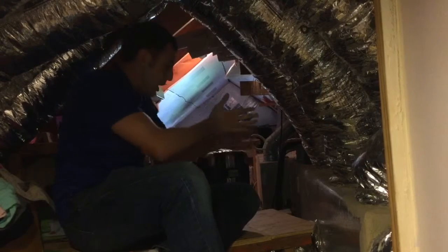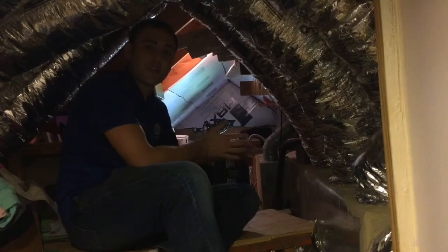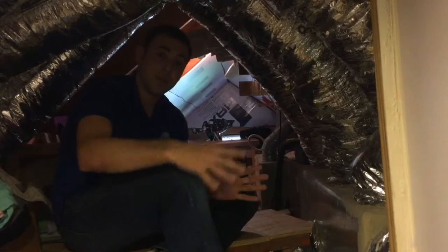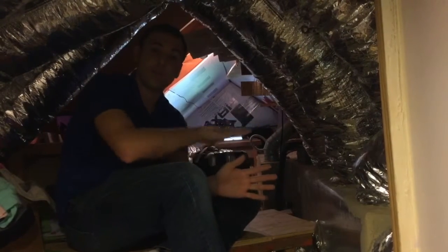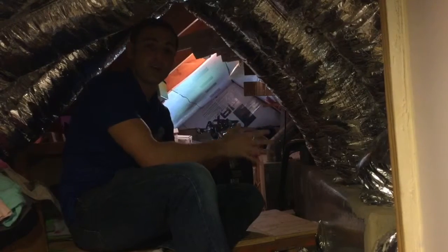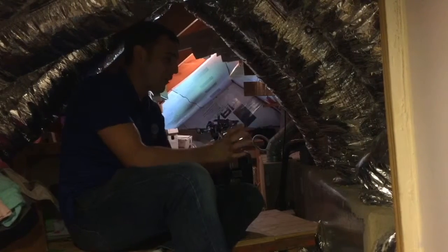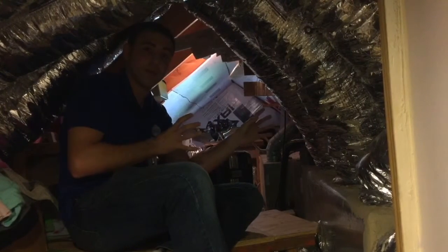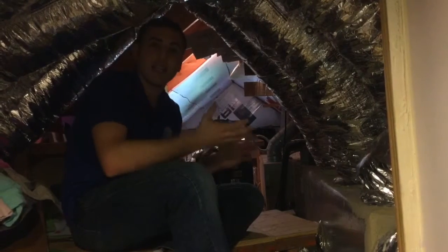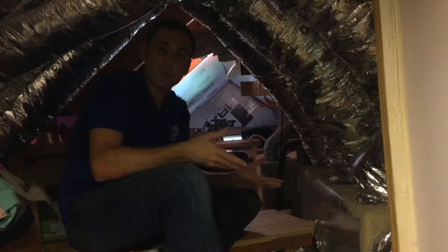Ideally, you want a third of the plenum in the beginning to be completely blank, left alone for the air to sort itself out when it comes out through the coil. Then you want a third of the plenum at the end to be blank again so that there can be a good pressurization zone so that everything gets evenly pressurized in the middle third, which is where you're going to put all of your ductwork. And when you put your ductwork on, you really want to stagger it and you want to separate them as much as possible so that they aren't fighting for the air and that one doesn't get an unequal amount of air than the other. So all of those things are ideally what you want to do.